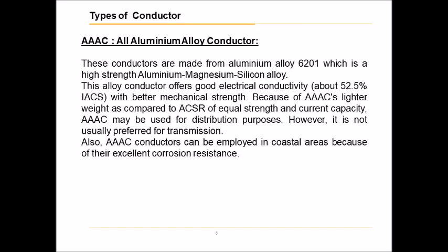AAAC — all-aluminium alloy conductor. These conductors are made from aluminium alloy 6201, which is a high-strength aluminium-magnesium-silicon alloy. This alloy conductor offers good electrical conductivity, about 52.5% IACS, with better mechanical strength. Because of AAAC's lighter weight compared to ACSR of equal strength and current capacity, AAAC may be used for distribution purposes.